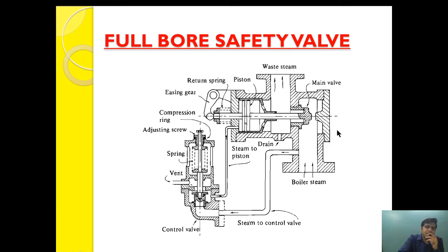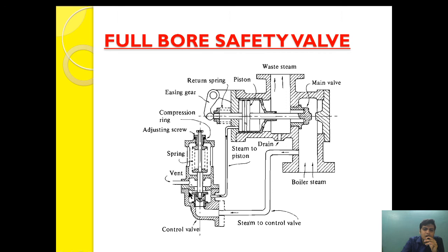As you can see in this design, the return spring is not in direct contact with the escaping waste steam, and hence it prevents distortion of the spring. Second, because the operating piston area is much larger than the main valve, it provides sharp opening. Sharp closing of the valve is provided with the help of the return spring. The operational control is provided by the control valve, which has a vent that vents the top part of the system when the valve is closed.